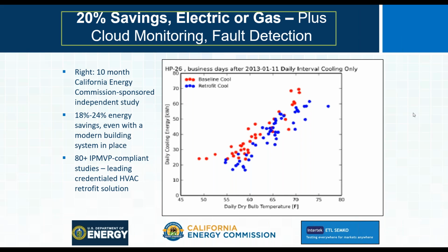This graphic is from a 10-month gold standard study commissioned by California Energy Commission, conducted in San Diego, so you get 10 months of cooling. The x-axis is daily dry bulb temperature in degrees Fahrenheit, and the y-axis is daily energy consumption. These were heat pumps — blue is with our PACE node online, red is retrofit offline. Fair aligning through those, the independent engineering firm found 18% to 24% savings with absolute maintained set points in a modern flex office manufacturing building with an existing building management system. That's what we've been able to deliver, and that's why we're really excited to be working with Con Edison.